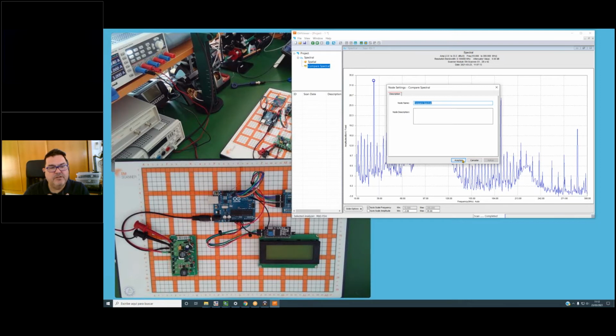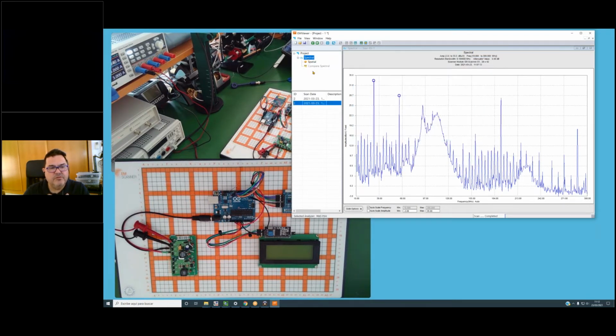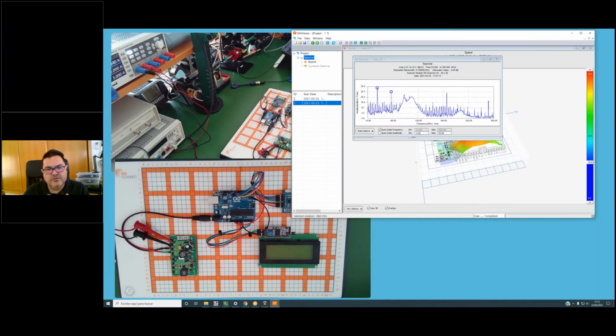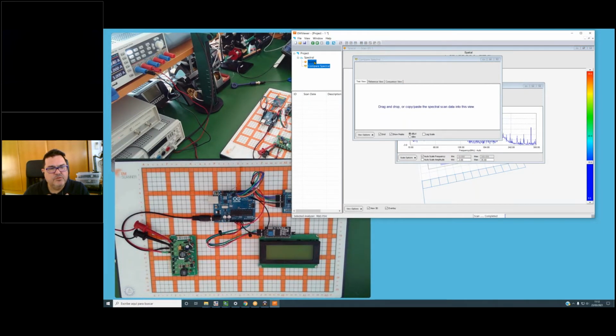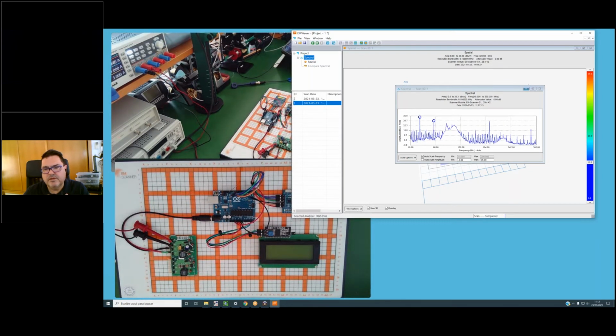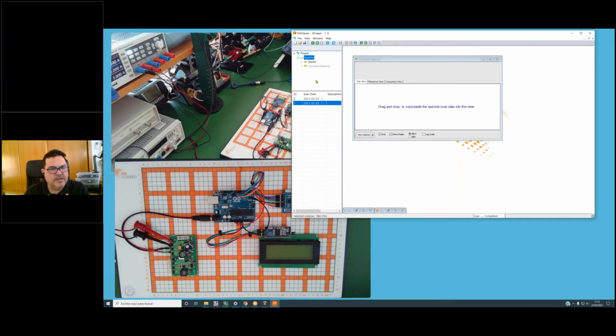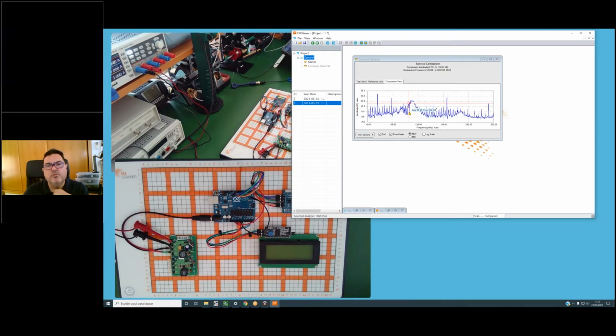When you select the spectral comparison inside of this window, you can introduce here the results of your spectral. Let me reduce this one and reduce this one. And we can go here to the spectral, and we can put the reference view, for example, with the system off. And in the test view, we put the results with the system on. So this is the results with the device under test on. This is the reference view, the system off, and the comparison view will remove one from the other. So this is really the difference between the device under test on and the device under test off.